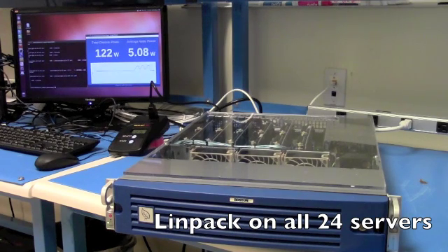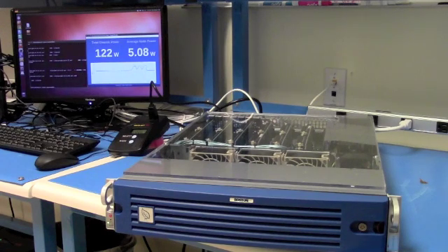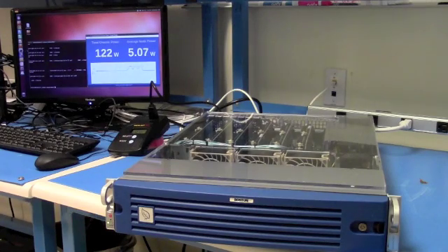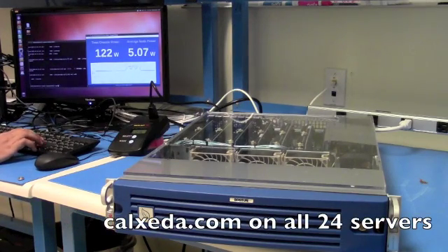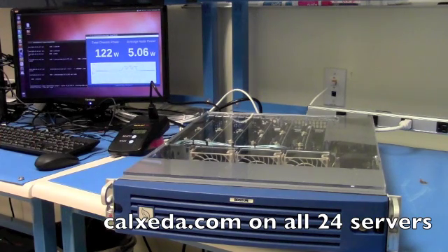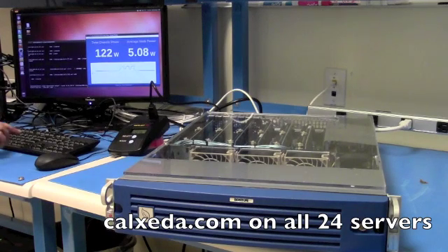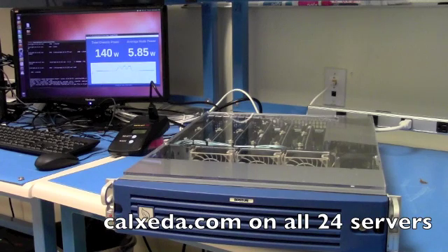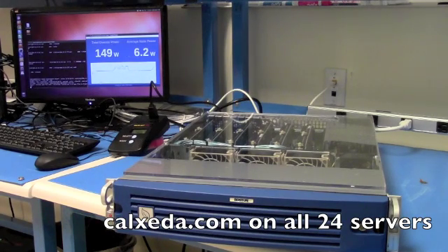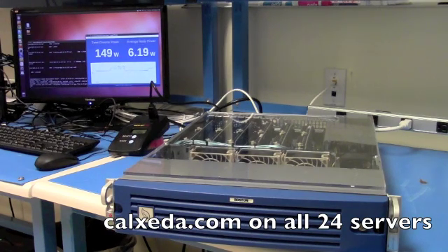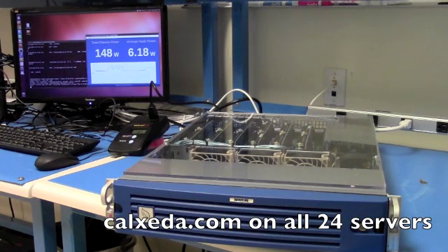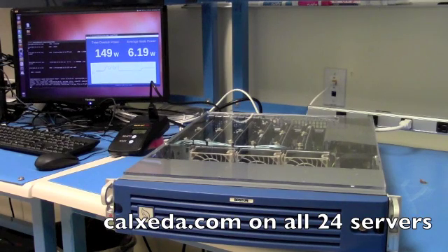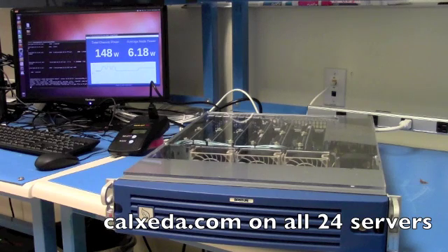So LINPACK isn't necessarily a realistic load 100 percent of the time. So we've also put a website together. We put the Calxeda website on all 24 servers. We're going to run this for you right now at 60 percent utilization. So the power goes from idle up to about 150 watts, about 6.2 watts at the wall. And that's about 4.5 watts of power usage of the individual servers themselves.